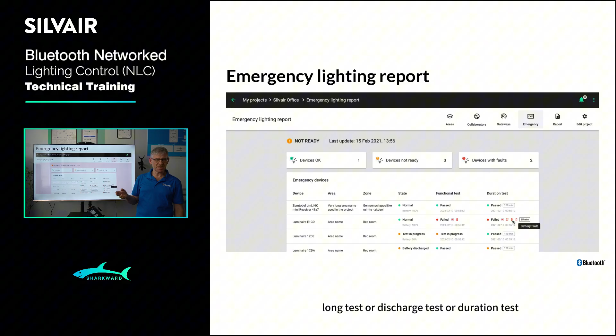How the emergency function looks like. There is scheduling, so you can schedule that the tests are run, for example, monthly. Every Saturday morning, the emergency fixtures are running the so-called short test or functional test. And yearly, every 52 weeks, they can run the long test or discharge test or duration test. There are different names for the same kind of test, which basically discharges the battery and measures the time.